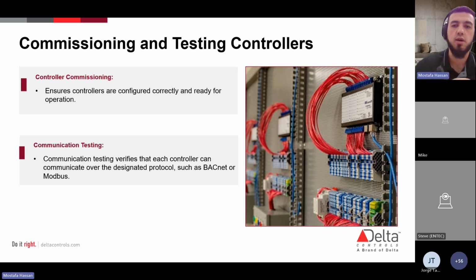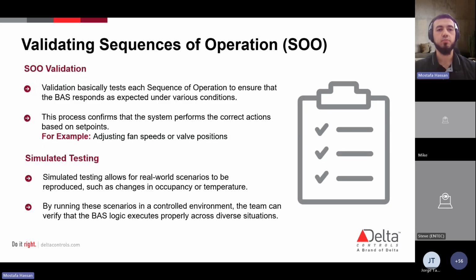Communication testing, right? Repeated a lot yesterday. Protocols, right? BACnet, Modbus, to make sure that each controller is actually communicating properly over the designated protocol, right? This is going to make sure that all components, the controllers, the sensors, and actuators are interacting seamlessly within the BAS network. And you're also allowing a smooth information flow and coordinated control.